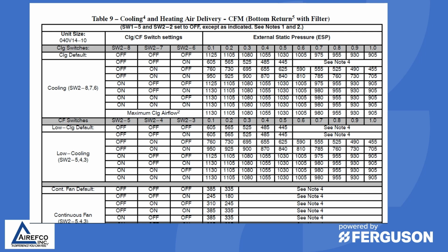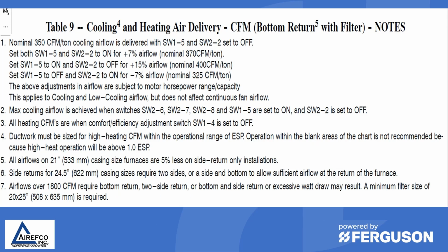So make sure that when you're installing a gas furnace and setting up the airflow, that the dip switches are set correctly for the CFM that you need for your application. Make sure that you read any notes that are attached to a table, such as the one in the previous slide, that tells you that with different dip switches you can add or subtract airflow to a gas furnace.